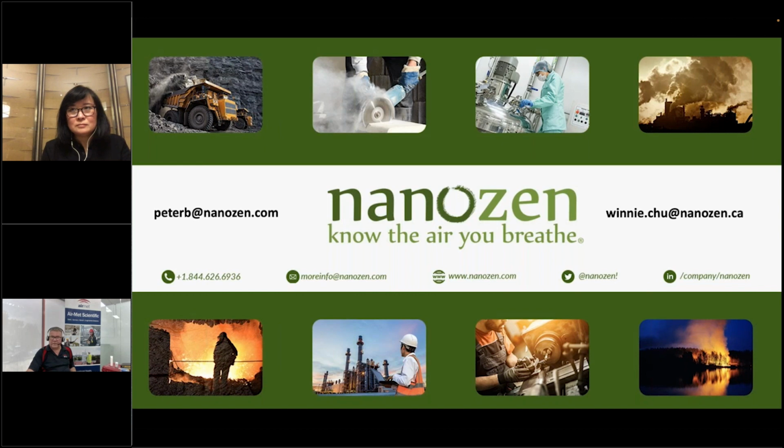Okay, I've got a few more here, Winnie. You mentioned you can calibrate the unit to specific mineral particulates. How many calibrations can you have at the same time, and can you monitor different minerals simultaneously? The SAS is designed to measure three buckets, plus the background. So you can specifically calibrate to determine three chemicals of your choice, and we dump everything else that isn't calibrated into one bucket. It's called other.